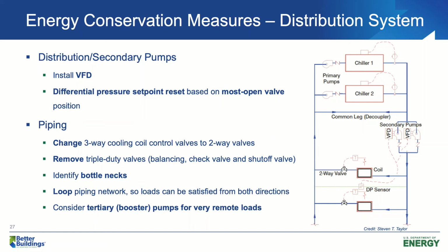Identify the bottlenecks. Loop piping network. What I mean here is that if you are thinking about decentralizing your chilled water plants, you can try to strategically locate your plants to minimize the total distance between your chillers and cooling loads. You can consider booster pumps for very remote loads. By doing this, your secondary pumps do not need to overpressurize all other cooling coils just to make the very remote cooling loads get enough chilled water.